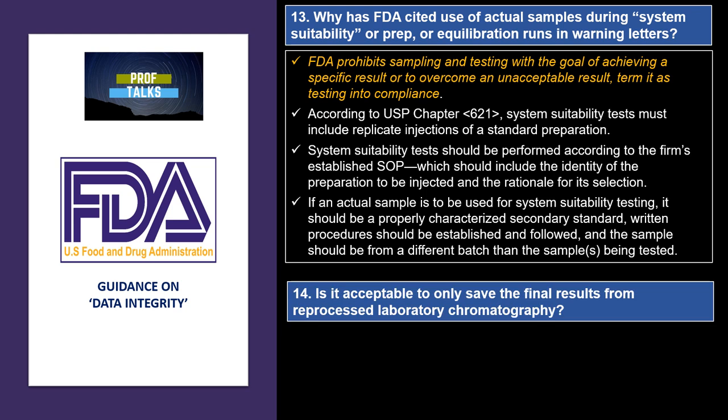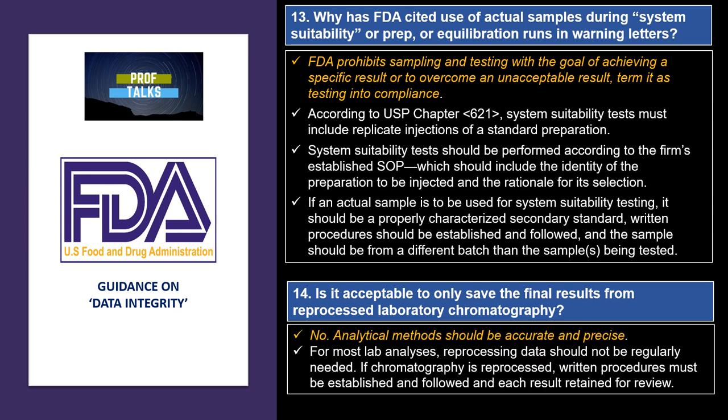Is it acceptable to only save the final results from reprocessed laboratory chromatography? No. All analytical results should be saved, whether processed or reprocessed initially. Reprocessing should not be carried out routinely. If chromatography is reprocessed, a written procedure must be established and followed, and each result should be retained for review.